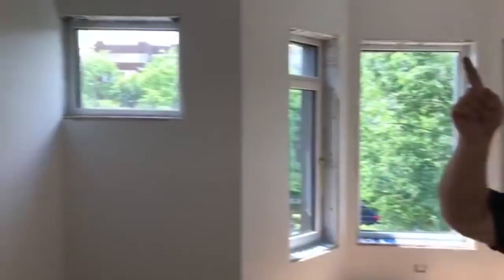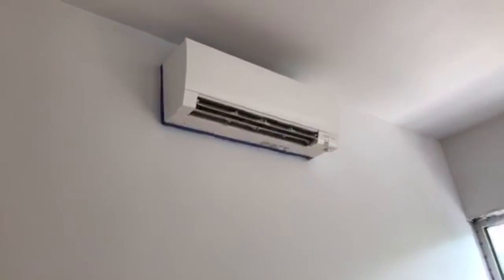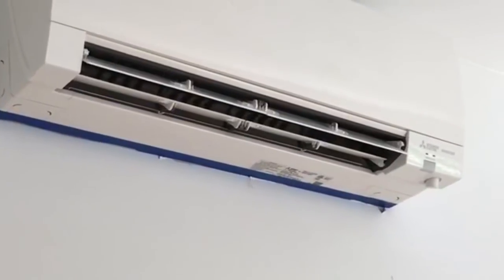The interesting thing is these Mitsubishi units and this Mitsubishi system have a coefficient of performance of greater than 3. Depending on the ambient air temperature and other factors, the productivity of the unit ranges from 3 to 4.5. But at 3, the math gets simple. If you have 6,000 kilowatt hours of heating and cooling demand over the course of a year to maintain the design temperature, and your system is rated at 3, 6,000 divided by 3 means 2,000 kilowatt hours of energy.